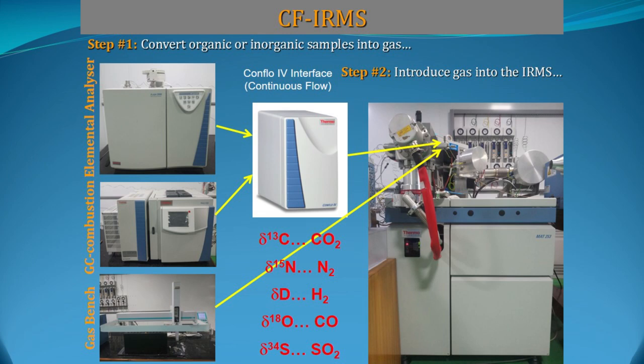In our institute we have a continuous flow isotope ratio mass spectrometer, which is a gas source mass spectrometer. This means we require gaseous samples, but in the field we collect either solid samples or liquid samples like water. To produce gas we use peripheral parts like elemental analyzer, GC combustion or GC IsoLink, and gas bench. Through these peripheral parts we produce different gases like CO2, nitrogen, hydrogen, and carbon monoxide.